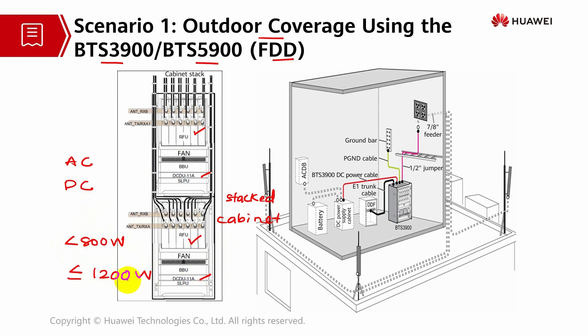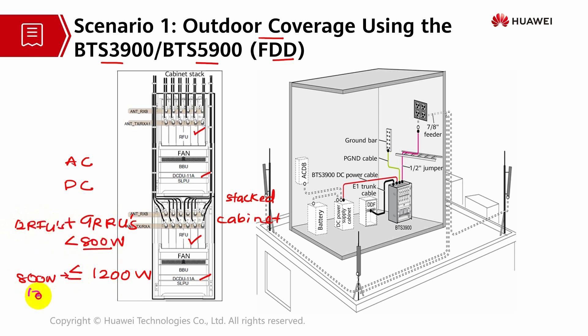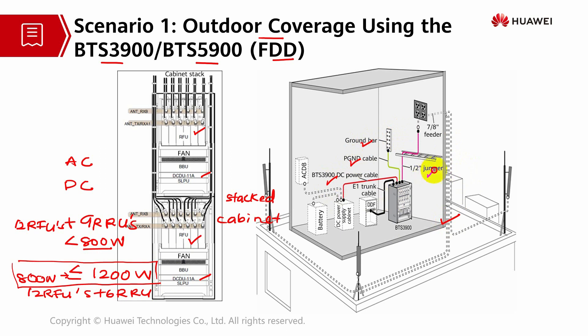Power consumption depends on how many circuit breakers are used. Using a conversion-type power module like EPU, power consumption can be between 800 and 1200 watts. For example, nine RRUs gives less than 800 watts, while 12 RFUs plus six RRUs results in 800 to 1200 watts. The diagram shows the full setup including grounding cables, ground bar, DC power cables, jumpers, feeders, and other connections.